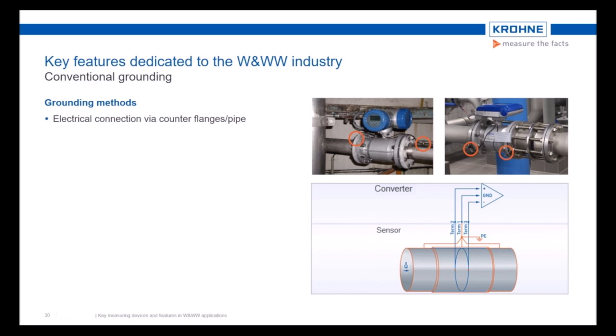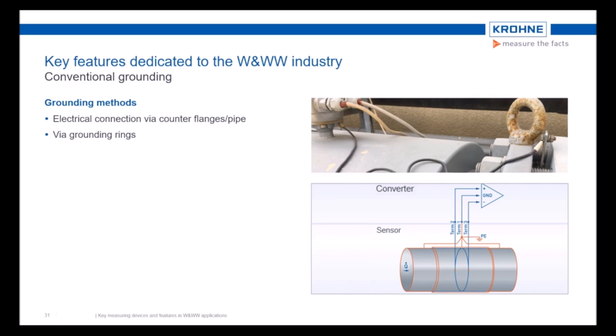So the most common method is to realize it via the counterflanges. Requirement for this is that the counterflanges have a conductive contact to the media, which means that the pipe should not be coated. If the counterpipe is coated and therefore has no conductive contact to the media, you normally use grounding rings, which are like washers to realize the conductive contact. The grounding cables will be connected to the grounding rings in this case. So you may consider resistiveness of the material of the grounding rings, which is of course dependent on the media in the pipe.